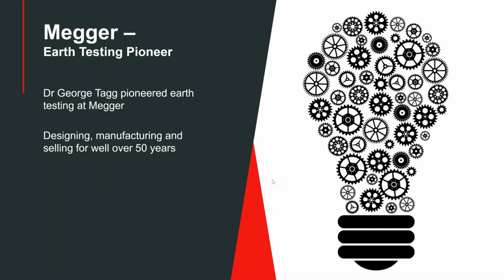And that's exactly what they did. So they went from high resistance and high voltage down to low resistance and low voltage, and modified it so that you could use a tester to test the efficiency of your grounding electrode. Next.